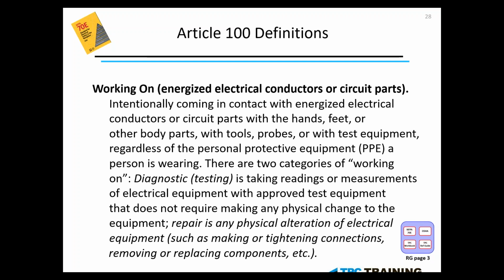Now, this is broken up into 2 categories. Diagnostic testing is taking readings or measurements of electrical equipment with approved test equipment that does not require making any physical change to the equipment, and repair. Repair is any physical alteration of electrical equipment, such as making, tightening connections, removing, replacing components, and so on.